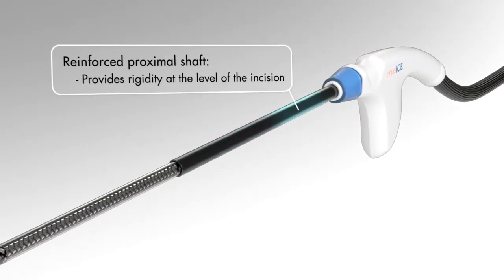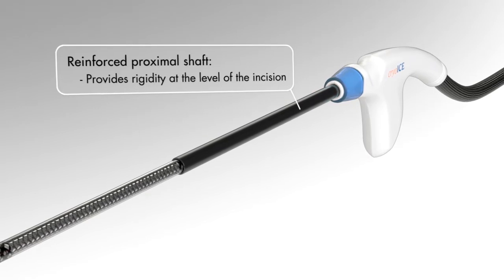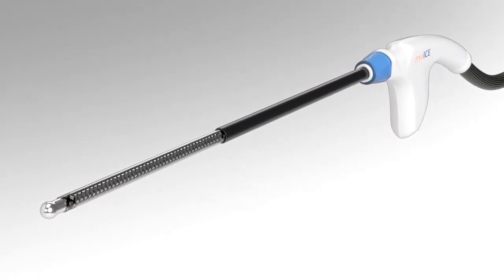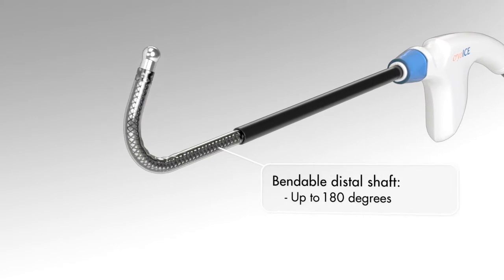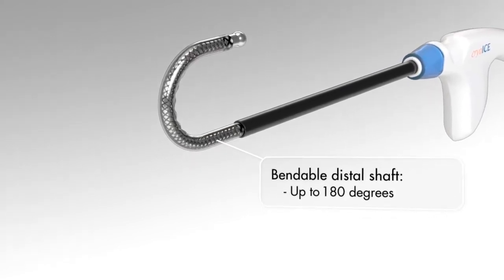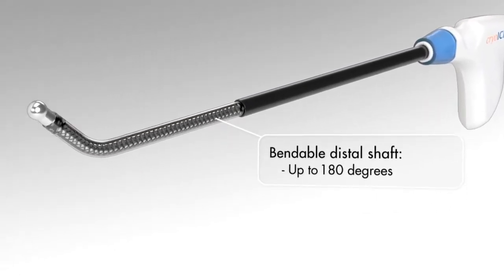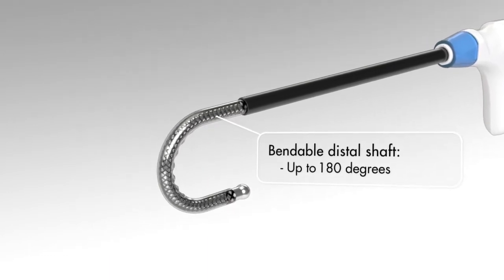The reinforced proximal shaft provides rigidity at the level of incision points such as a trocar, robotic service port, or thoracotomy. The bendable distal shaft is designed to be bent up to 180 degrees with a provided tool while maintaining the ability to deliver adequate pressure to the intercostal nerve.